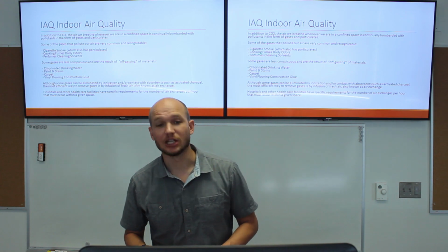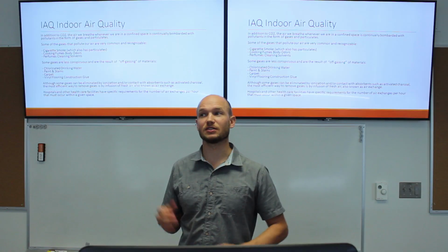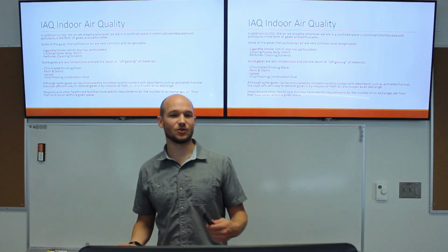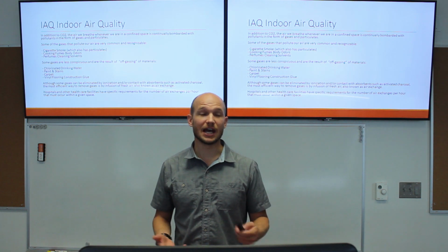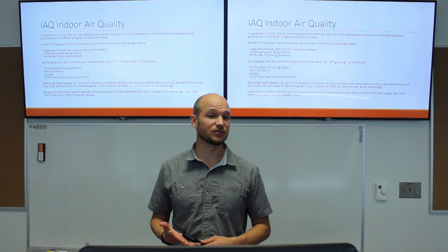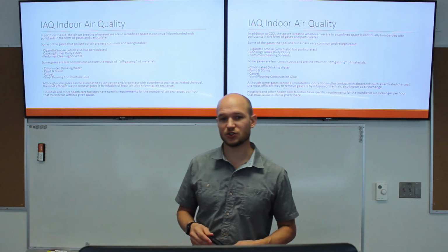There's chlorinated drinking water, there's paint and stains, there's carpet, there's vinyl flooring, construction glue. So there's a lot of things that you might not think about. These are all being released into the air as it heats and cools and settles, and there's dust, and so that's important to know, and that's why we bring in outdoor air. Hospitals and healthcare facilities are going to have specific requirements for the number of air exchanges per hour.